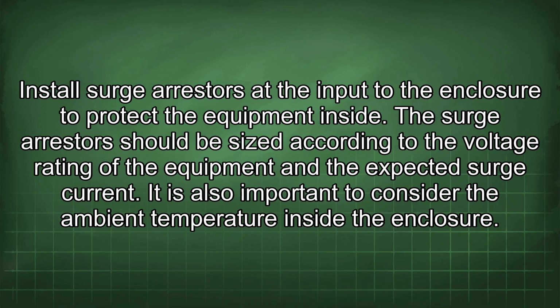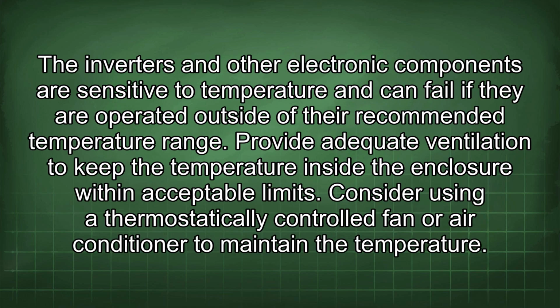It is also important to consider the ambient temperature inside the enclosure. The inverters and other electronic components are sensitive to temperature and can fail if they are operated outside of their recommended temperature range. Provide adequate ventilation to keep the temperature inside the enclosure within acceptable limits. Consider using a thermostatically controlled fan or air conditioner to maintain the temperature.